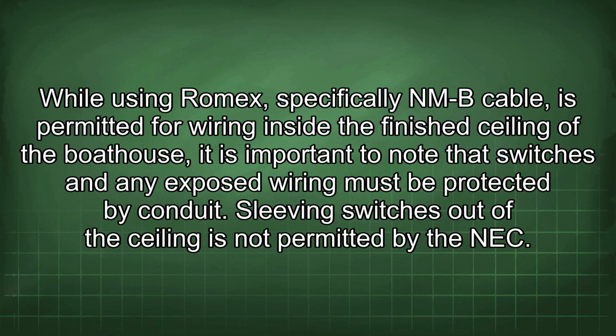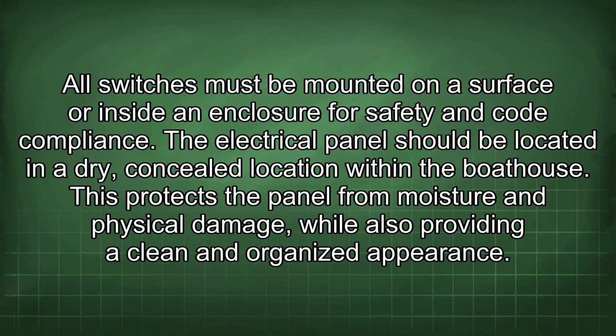shock. While using Romex, specifically NMB cable, is permitted for wiring inside the finished ceiling of the boathouse, it is important to note that switches and any exposed wiring must be protected by conduit. Sleeving switches out of the ceiling is not permitted by the NEC. All switches must be mounted on a surface or inside an enclosure for safety and code compliance.